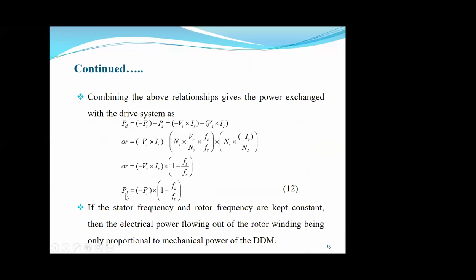Taking this equation, and treating the VFT like a transformer where ampere-turns at both sides are equal — NS into IS equals NR into minus IR — and evaluating these, we arrive at PD equals minus PR into (1 minus FS by FR), where FS is the frequency of grid 1 and FR is the frequency of grid 2. Since both grid frequencies are constant, this term is constant, so minus PR is directly proportional to PD, or PD is directly proportional to minus PR.